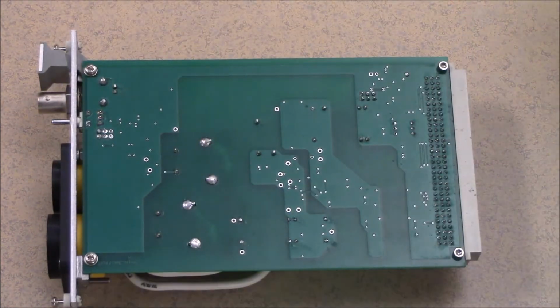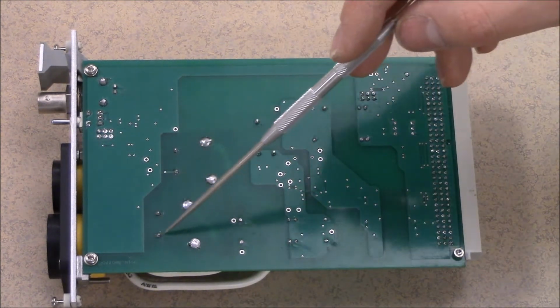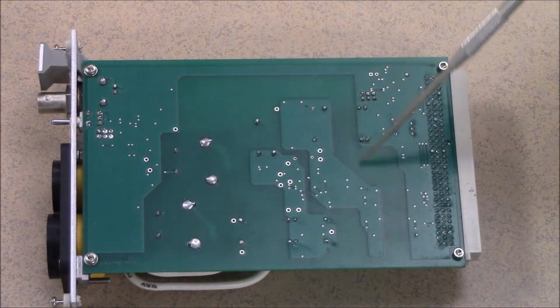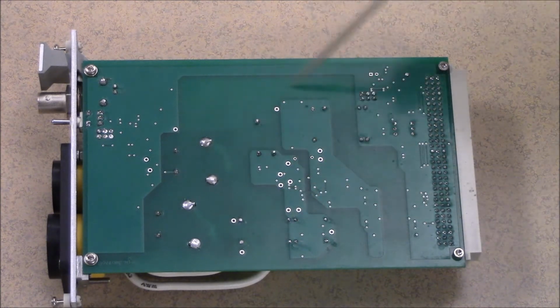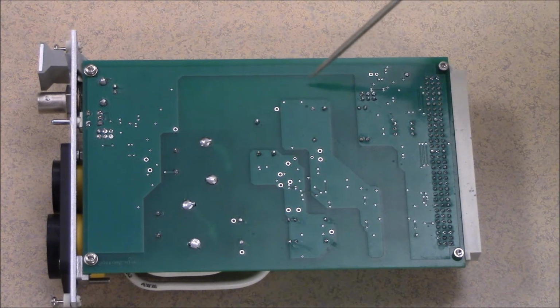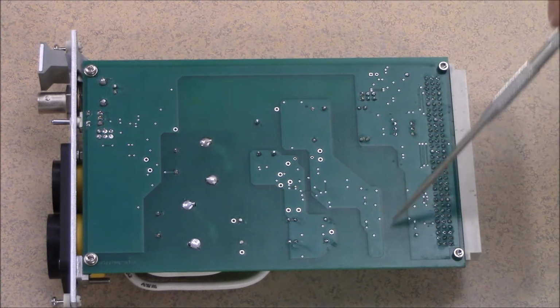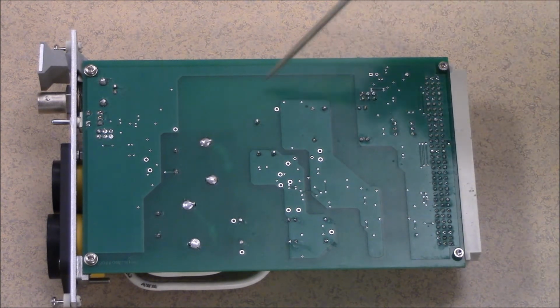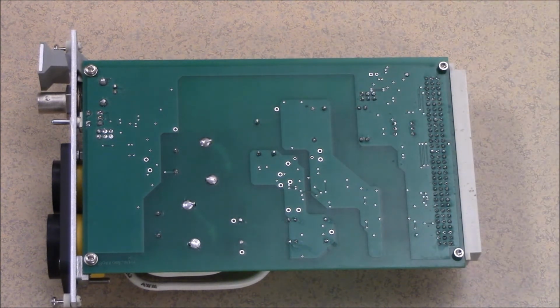Wide isolation distances, following recommendations from UL for an uncontaminated environment, were used to maintain at least 2500 volts of isolation, which follows the specification of our switching converter and our digital isolators. This is to prevent problems in case of lightning-induced surges or other such events.